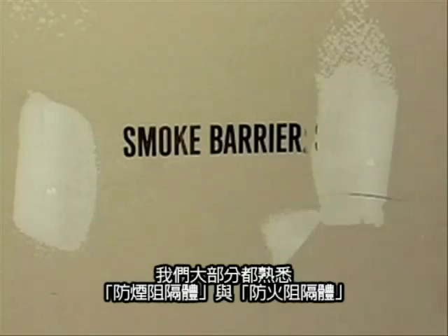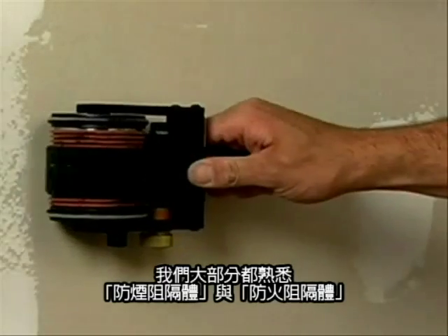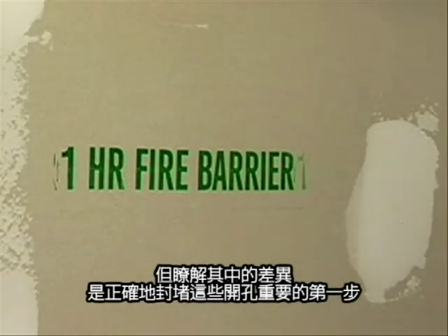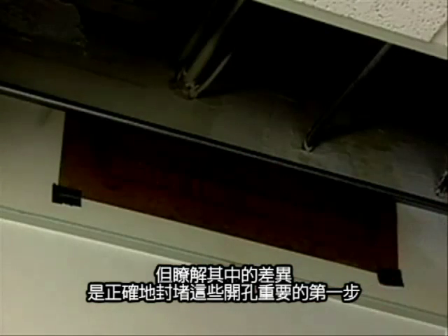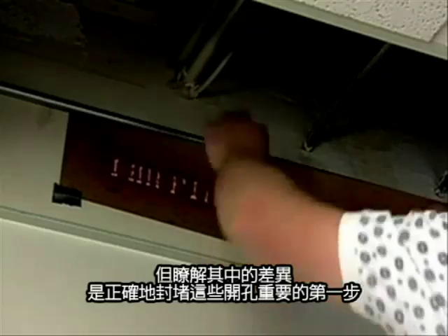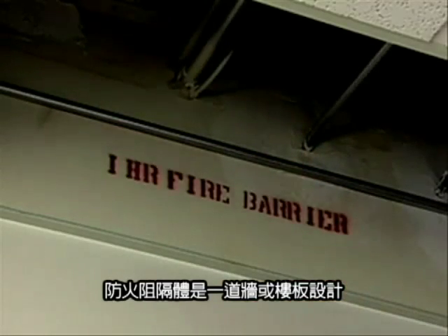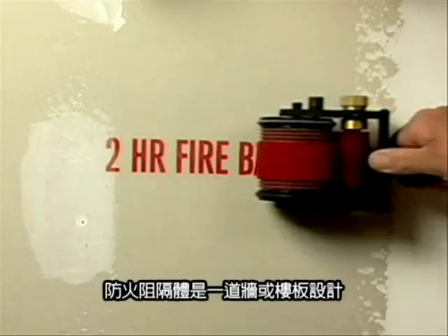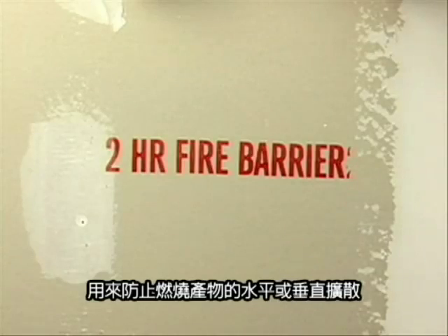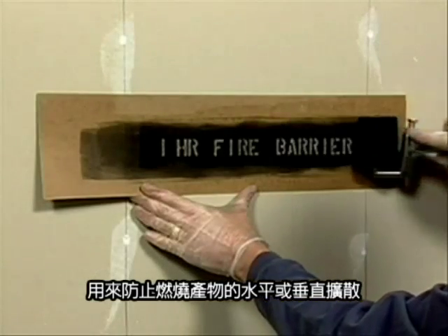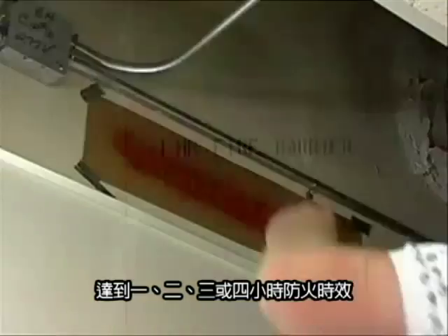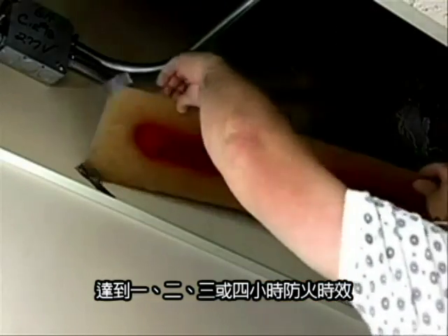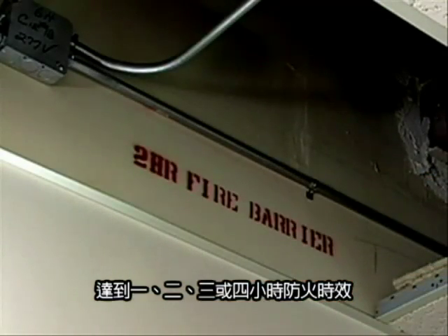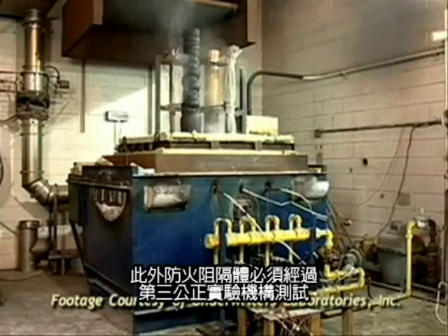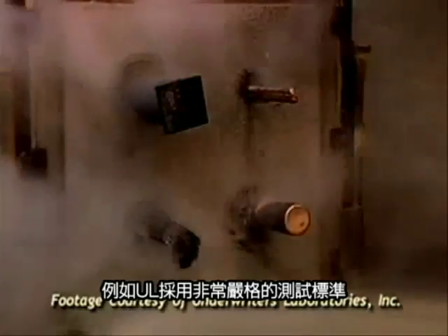Most of us are familiar with the terms smoke barrier and fire barrier, but understanding the differences is the critical first step in properly sealing openings in these barriers. A fire barrier is defined as a wall or floor designed to prevent the products of combustion from spreading vertically or horizontally for a period of 1, 2, 3, or 4 hours. Additionally, a fire barrier must be tested by a third-party laboratory such as UL to very rigorous test standards.